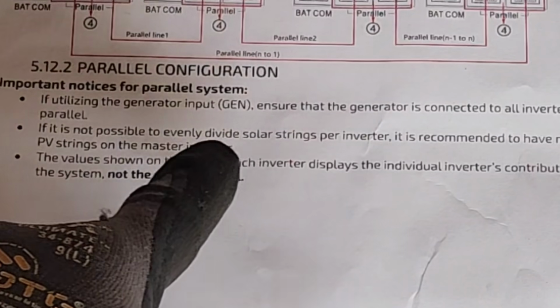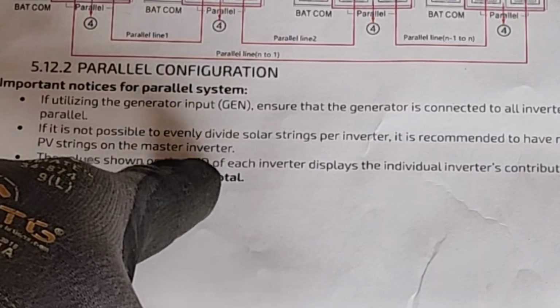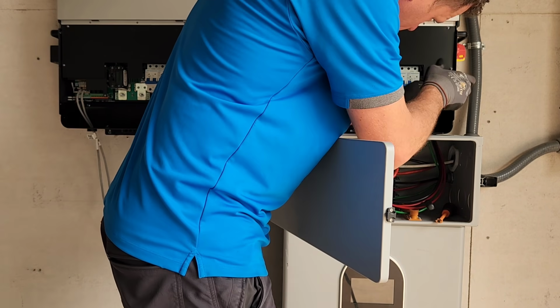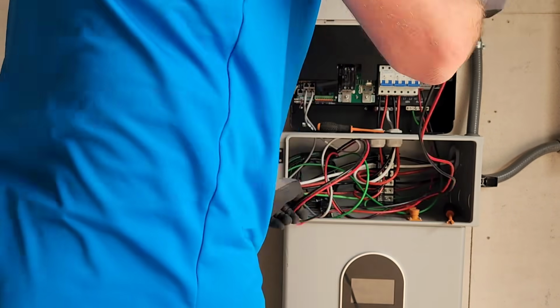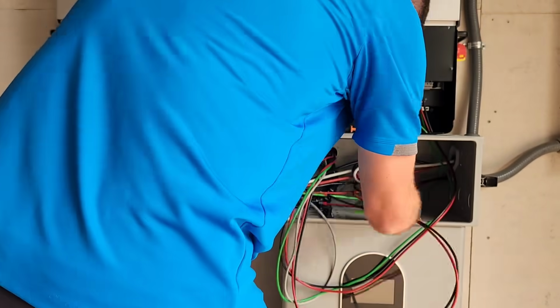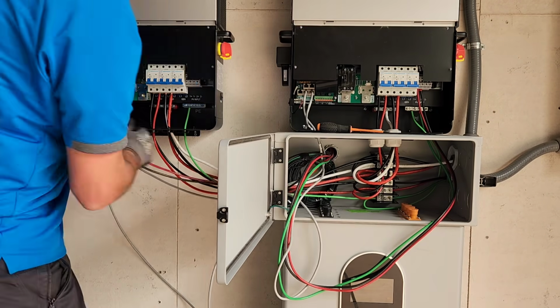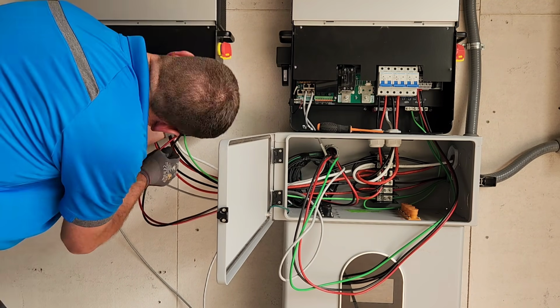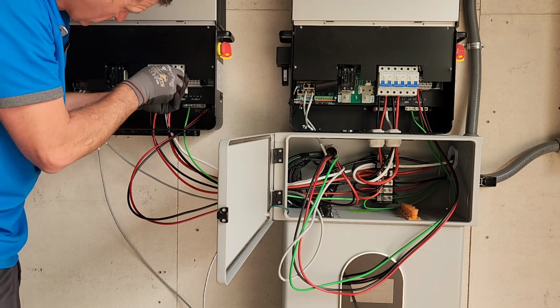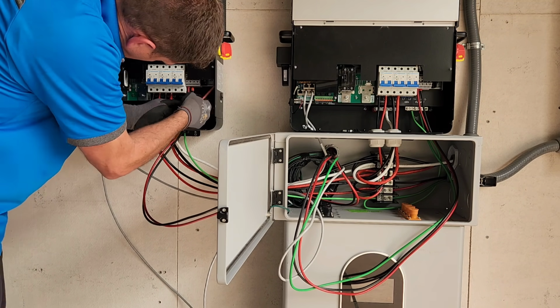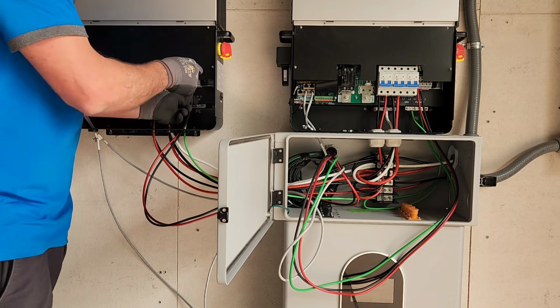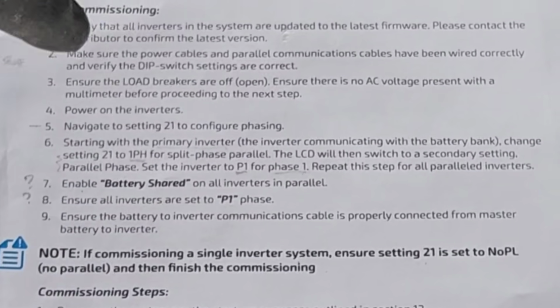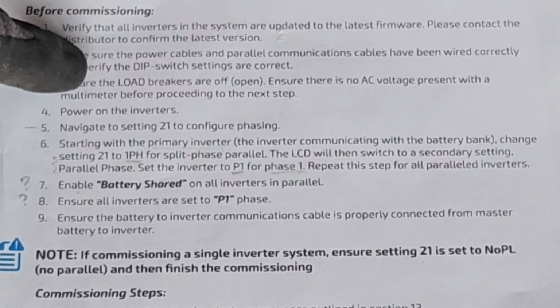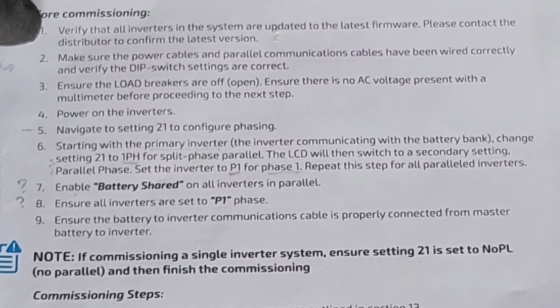I've got 2 solar strings, so it said I should divide them evenly and put the more powerful one on master. I have a solar shutoff near my solar array, so I'm thankful for that, or I would have about 400 volts waiting for me at the end of these wires, so that wouldn't feel very good. The torque specifications for all these connections are in the manual. Okay, I need to verify that both systems are updated with the latest firmware. Let me hook up the battery cables and that communication cable to master right now and then check the firmware.